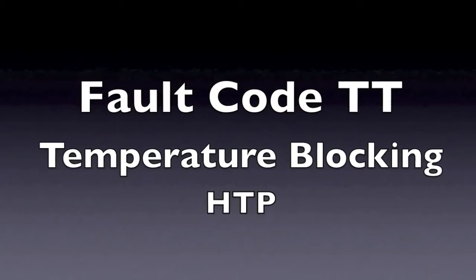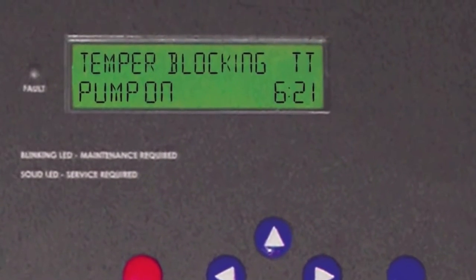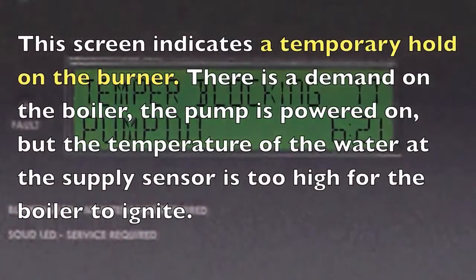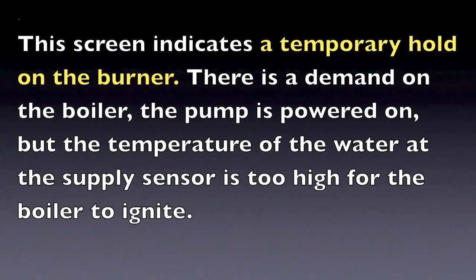If you are getting a temperature blocking code on your display, this code indicates that there is a hold on the burner from firing. On a boiler, this occurs because the water temperature at the supply sensor is higher than the set point in the boiler differential.